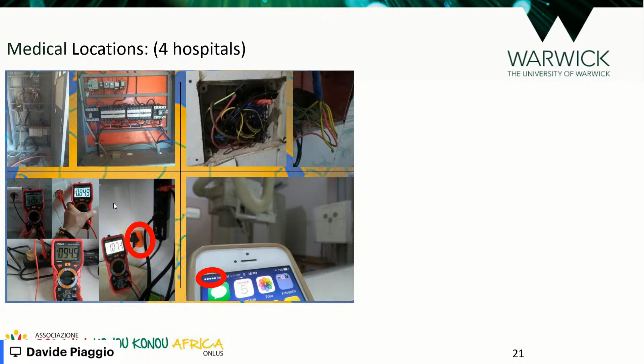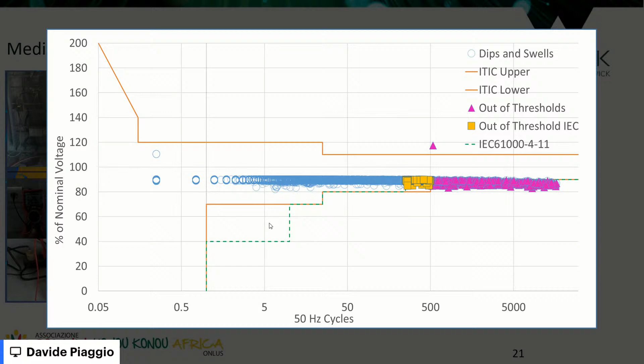So we also investigated the quality of this electricity. We used a voltage recorder from Fluke, and we recorded the voltage events in the sockets in the hospital. All these dots in the middle that you see here are events. What does events mean? They can be either sags or swells. When the voltage went over a certain amount or below a certain amount, it was recorded. These events have not only the voltage as a variable, but also the duration, and depending on the combination of the two, they can be potentially dangerous for the equipment.